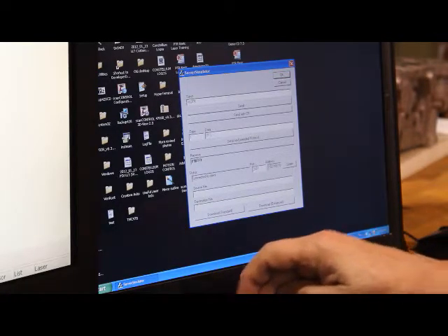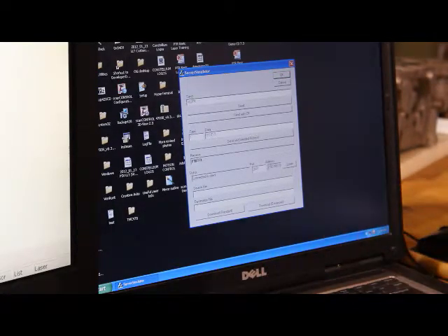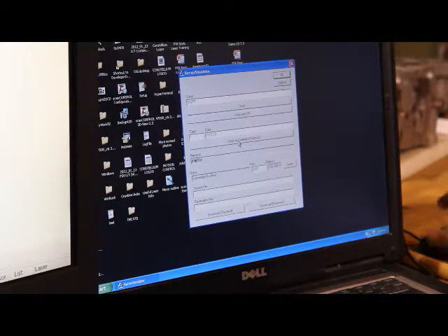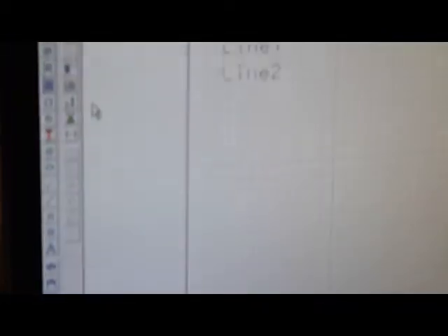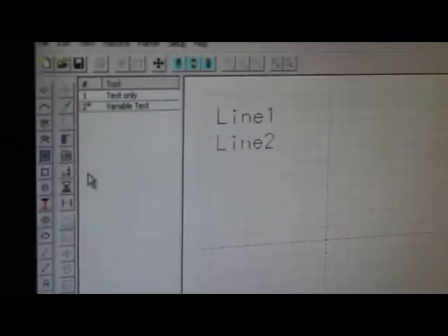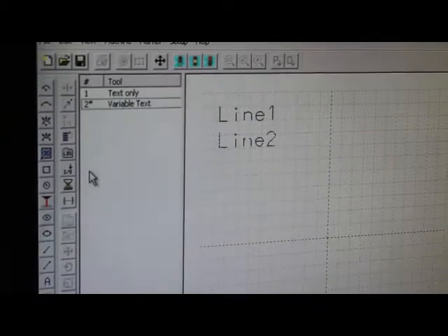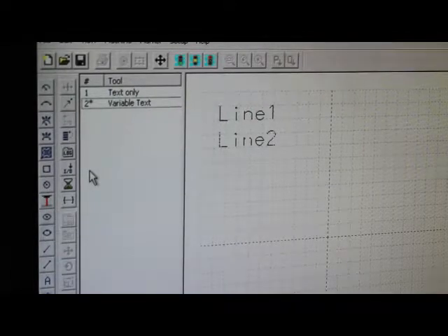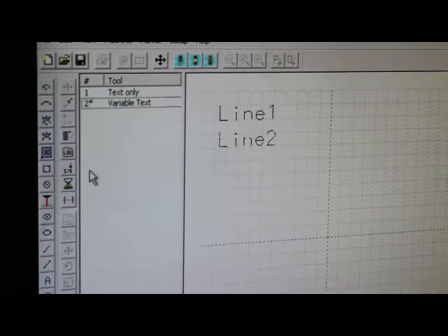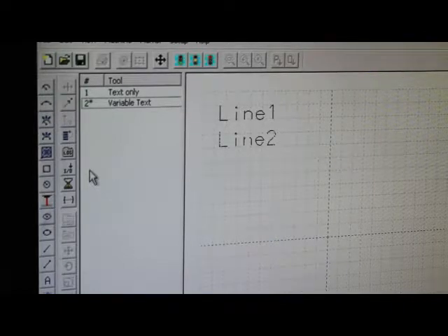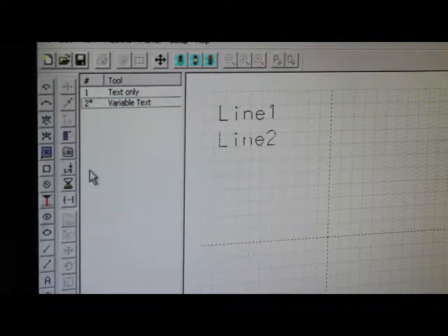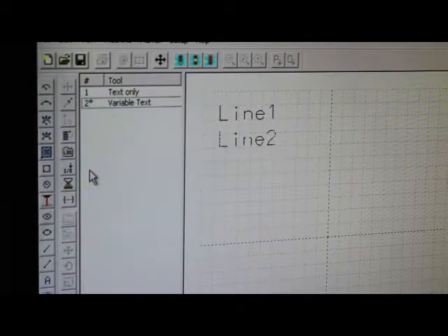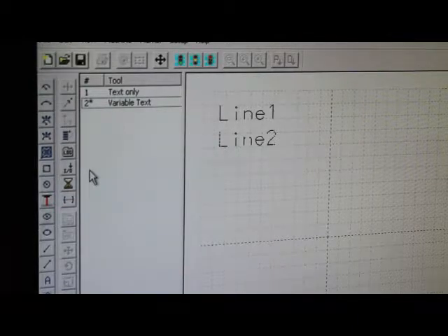And then I'm going to put in what I'm going to send. And the extended protocol, in this case, is very similar to your PLC, where it actually sends a number of control characters before it sends a text. The first thing it will send is something that's called start of header. This tells the receiving piece of equipment that a message is coming in. The next thing is going to be the message type.